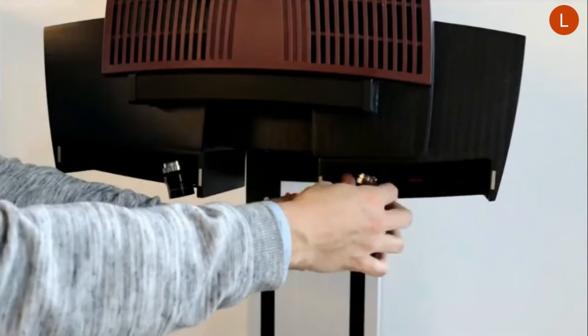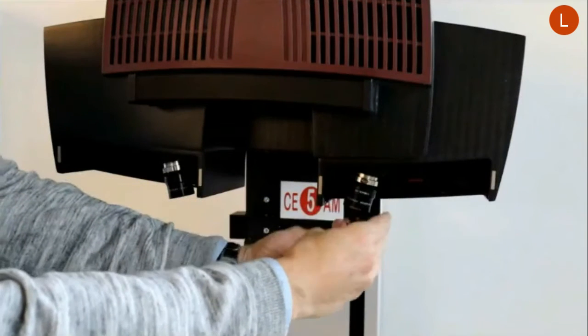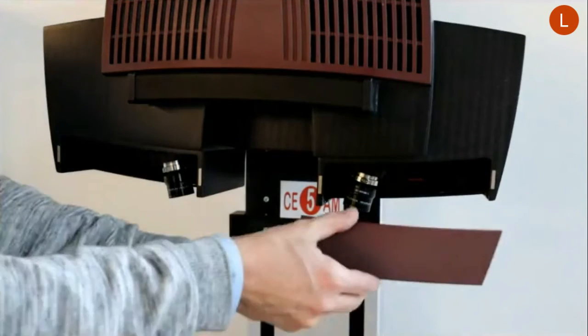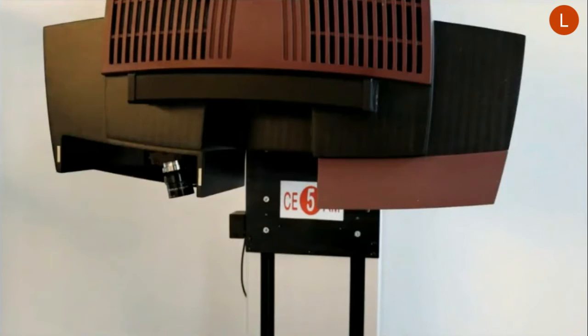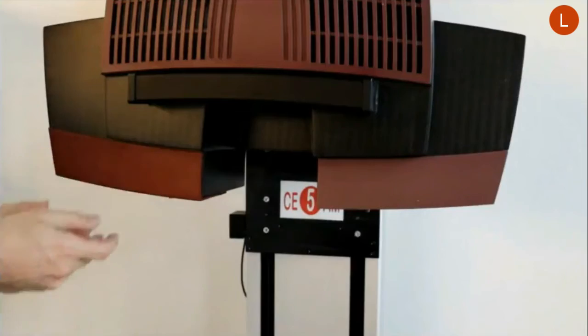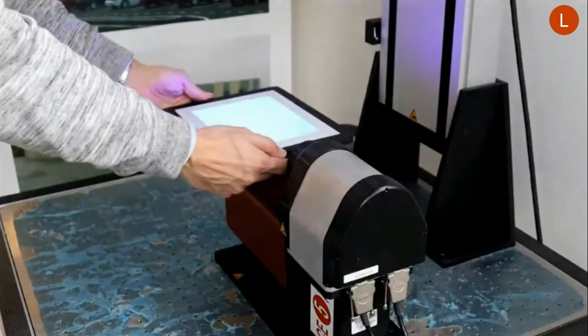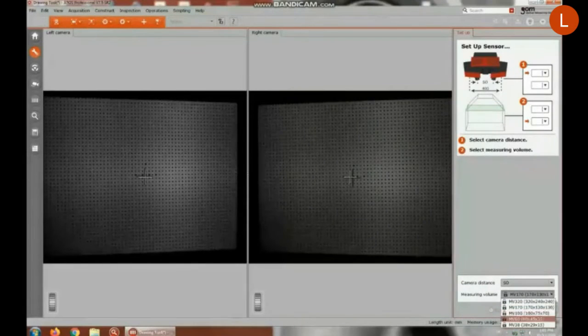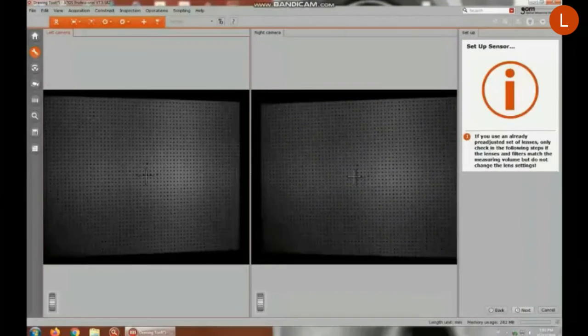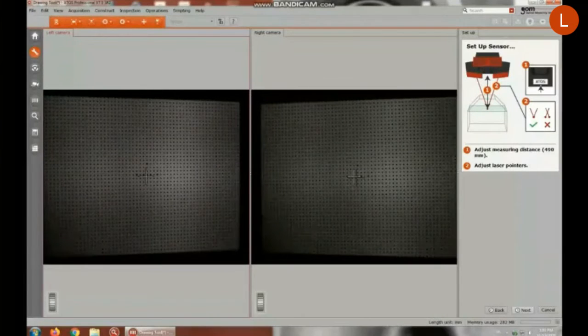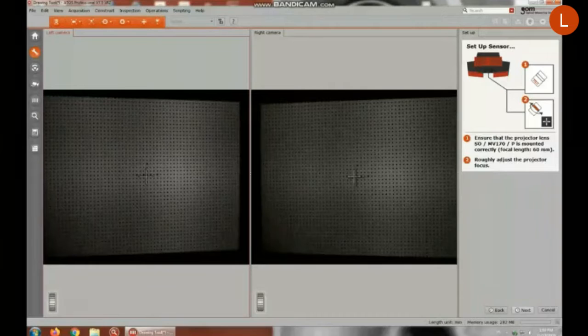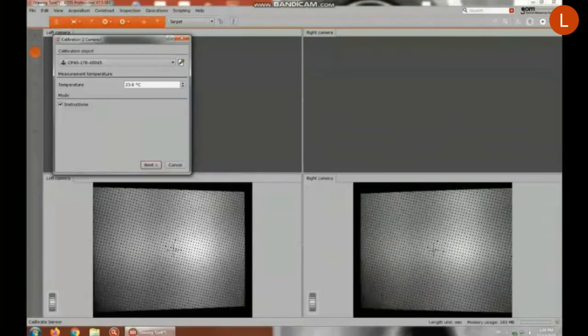The sensor unit is placed on a vertical lift unit, which allows remote control of the movement of the sensor unit to defined positions required during calibration. The covers of the scanning head are placed back. The calibration panel for the measuring volume 170 is magnetically clamped to the tilt and swivel unit. The measuring volume is determined in the software and other characteristics are checked before calibration. The tilt and swivel units start the reference run and the operator manually selects the appropriate calibration panel and enters the measurement temperature.